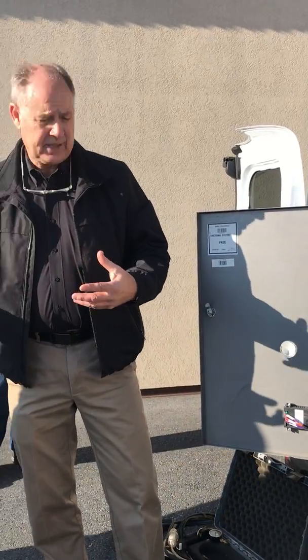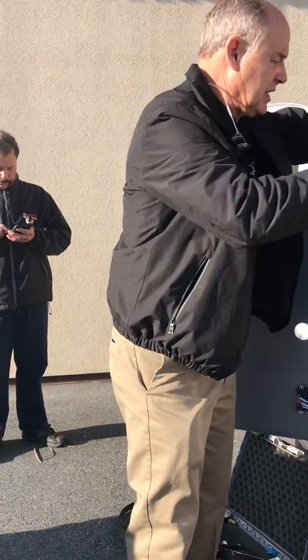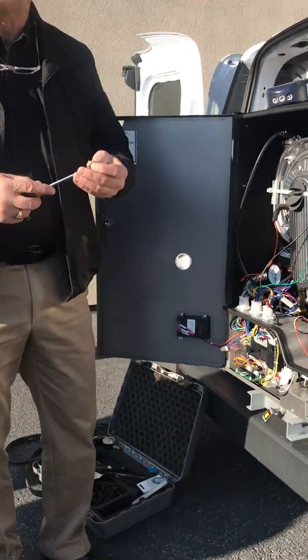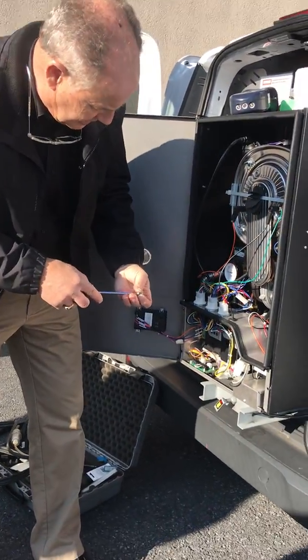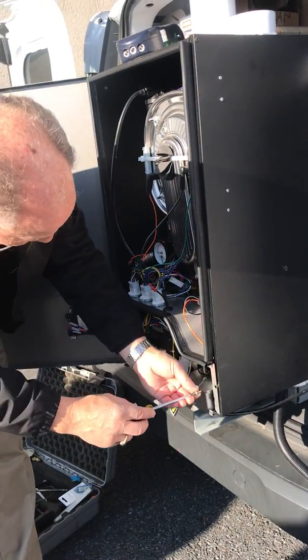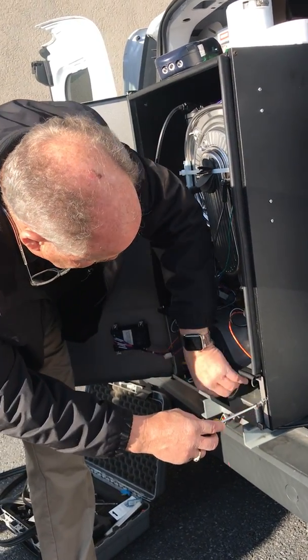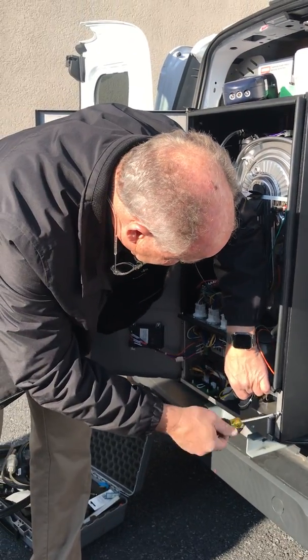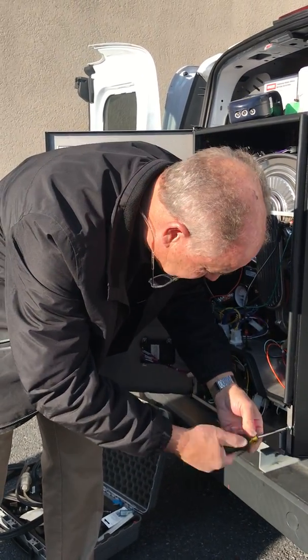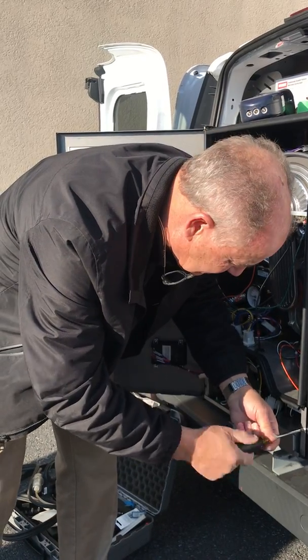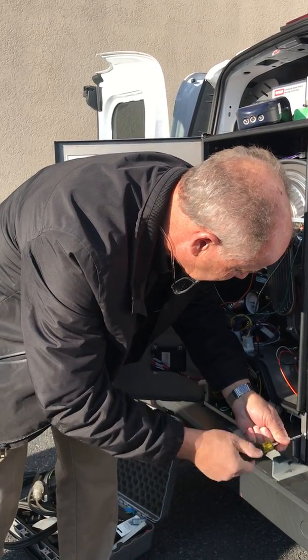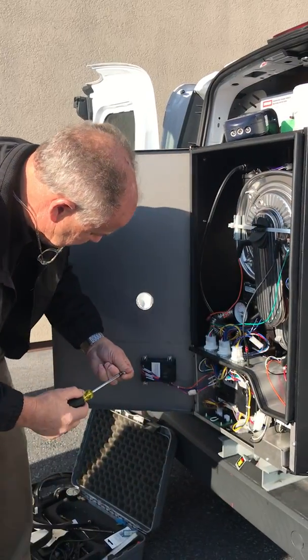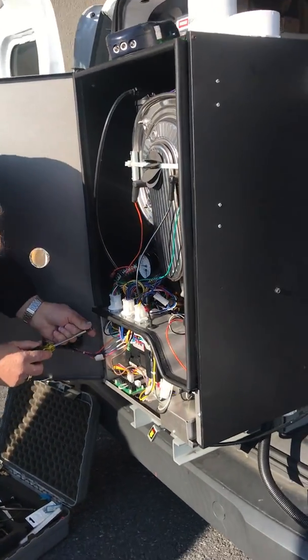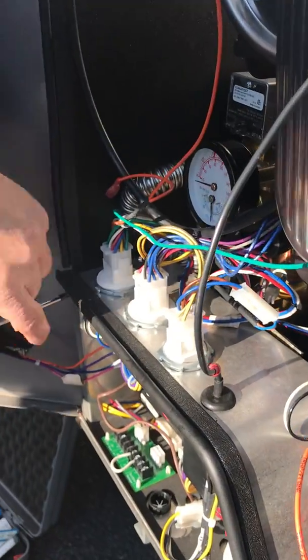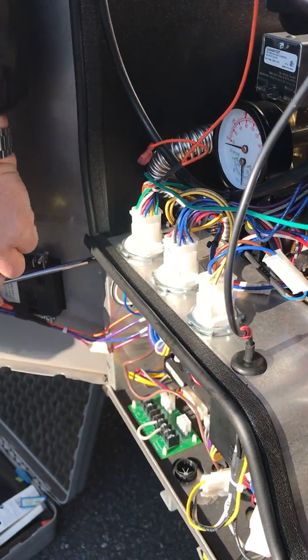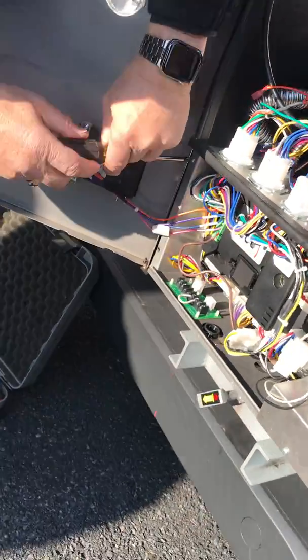We can actually pull the 24 volts out of this. There's the 2 end wires on that green plug here. We can pull 24 volts and power up our indirect. You can't power 6 zone valves, but we can do our indirect. So there's a little bit of 24 volts we can get when we need to do that. Hopefully when we go upstairs and go through some of the setups, this will all make a little more sense, a lot of what you can do with the control.